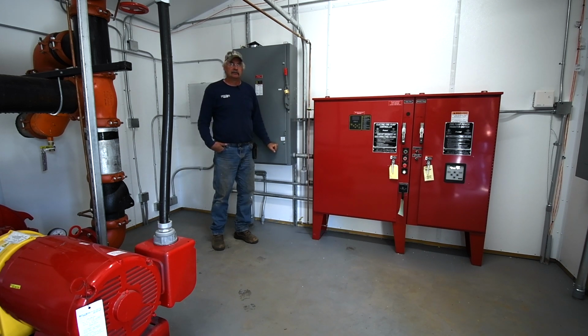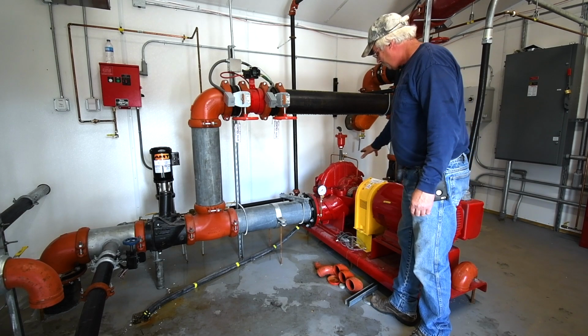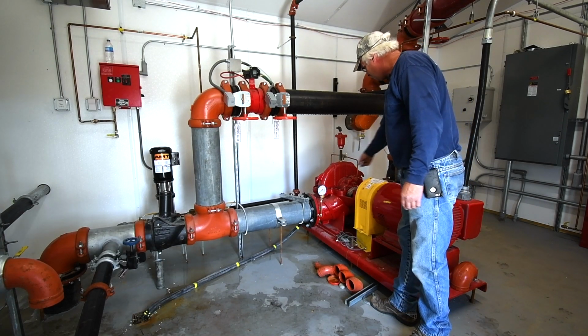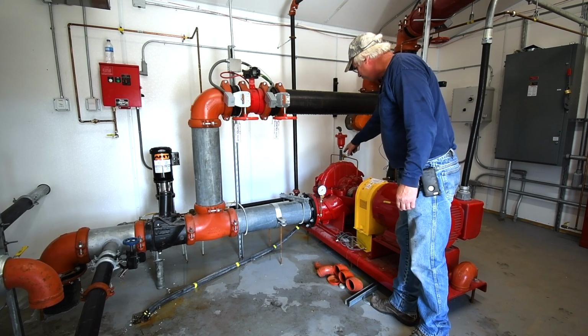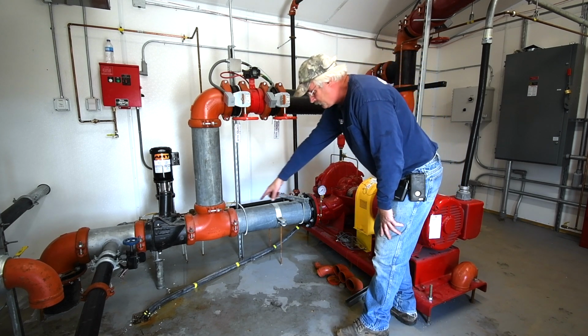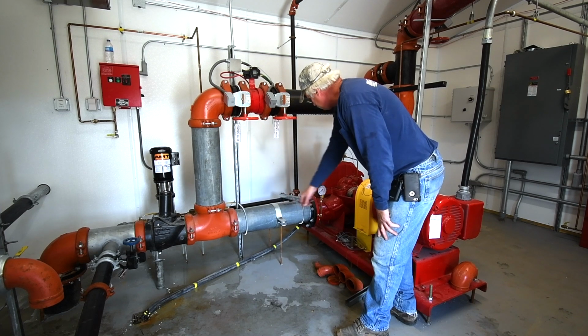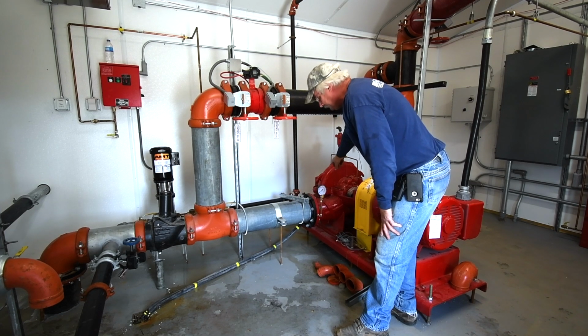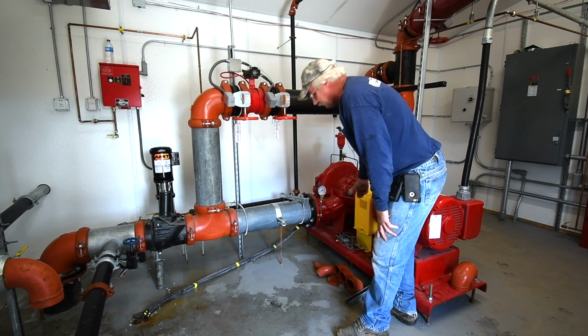Because this is the main disconnect for the fire pump controller. Our fire pump here is an electric fire pump. The water comes in, boosts the pressure up. There are 3 hoses on the backside leading to the floor drain. We've got 2 for packing that go down into the floor drain that want to bleed all the time.